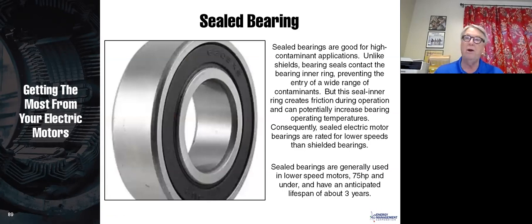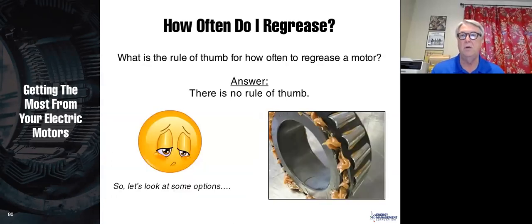This is a sealed bearing. There is no movement. Sealed bearings seem really nice because you never have to grease them, right? But they're only appropriate for lower speed motors. And sealed motors are generally used only 75 horsepower and under. And if you run a motor pretty much 24/7, you can expect a sealed bearing to last about 3 years because you can't re-grease. So if you want a bearing to last much longer than that, you should get a re-greasable bearing.